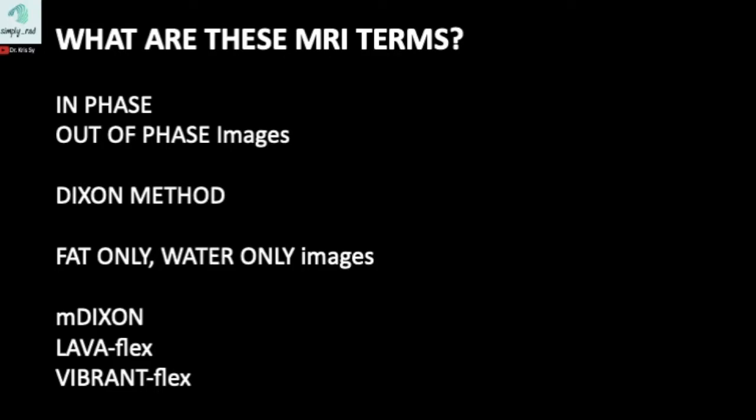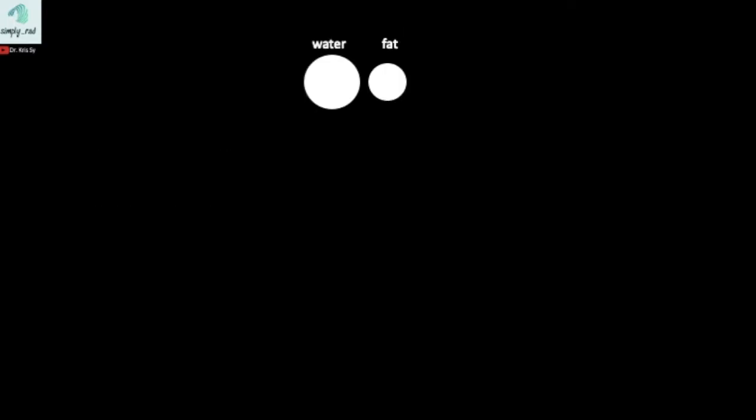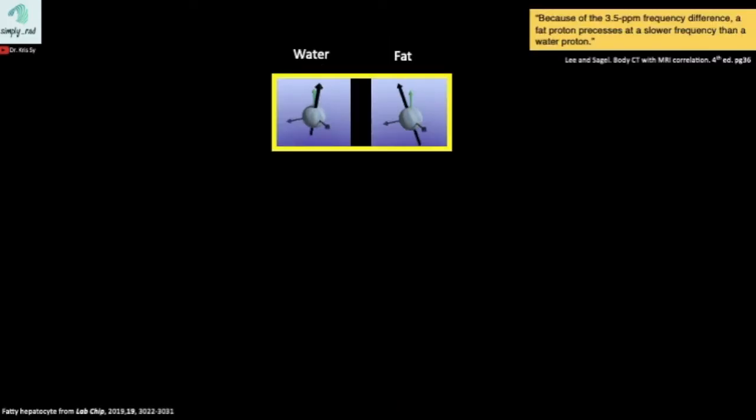First off, the in-phase and out-of-phase images. These circles represent the signals produced by the protons in water and protons in fat. Another way to look at it is imagining these spinning protons. The frequency of their spinning would differ. Fat here is slower than water.